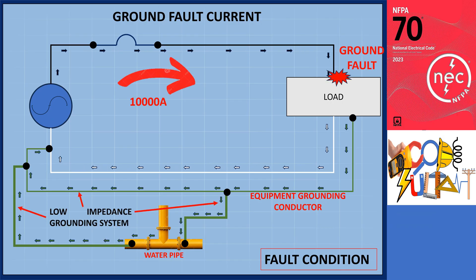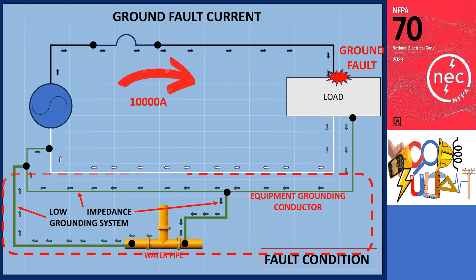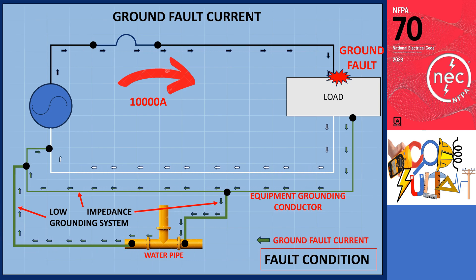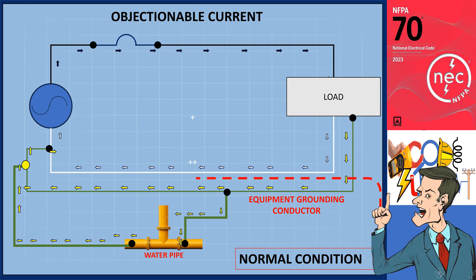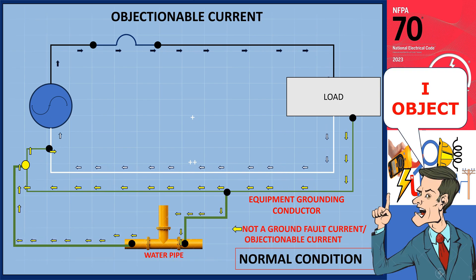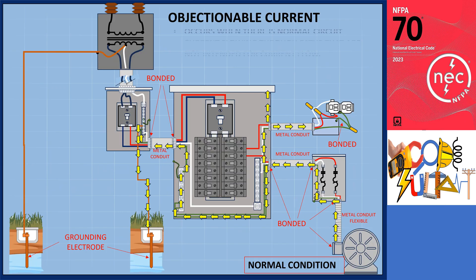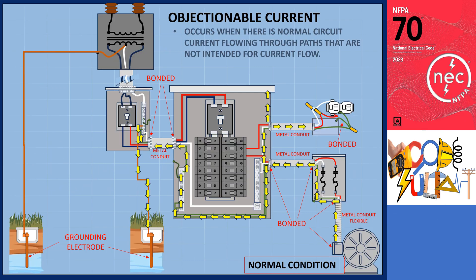During ground fault conditions, current flows through the equipment grounding conductor, which is known as ground fault current. However, what happens when there is current flowing through this path in the absence of a ground fault or a normal operating condition? This is what we refer to as an objectionable current. Objectionable current occurs when there is normal circuit current flowing through paths that are not intended for current flow, such as the equipment grounding conductor, grounding electrode conductor, metallic enclosure, and others.